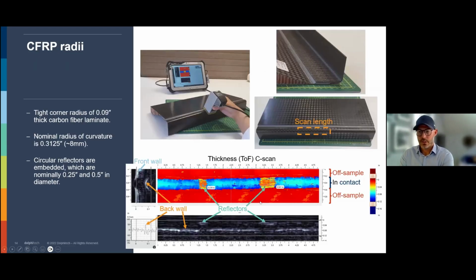Here's an example of a curved part. We have several transducers with several delay lines. This is a soft delay line, which is why you can put it on a curved edge here. You see there are a couple of inserts here actually, in this curved piece that we inspected. The blue is the back wall, so everything is healthy, and the red here are damages or inserts.